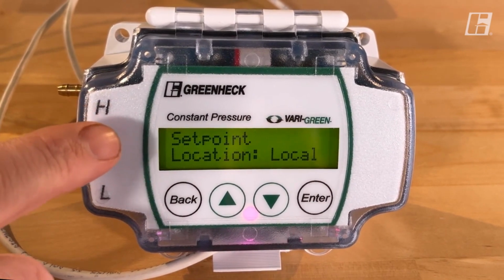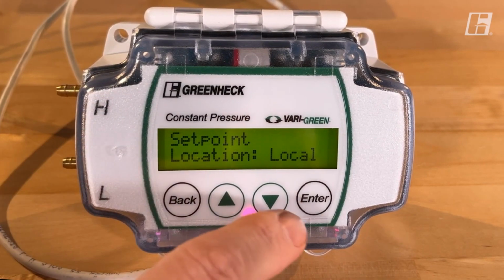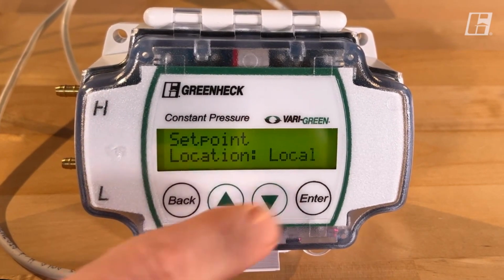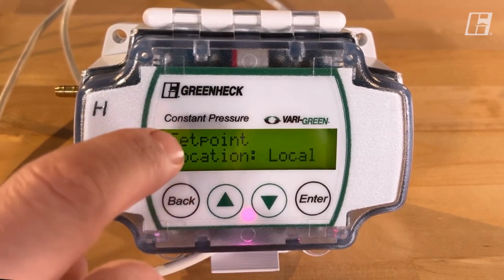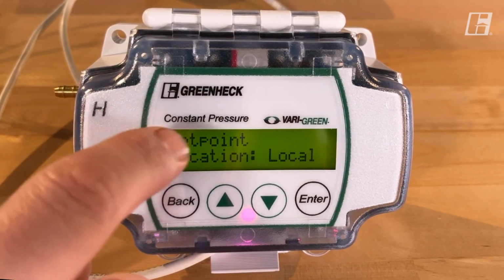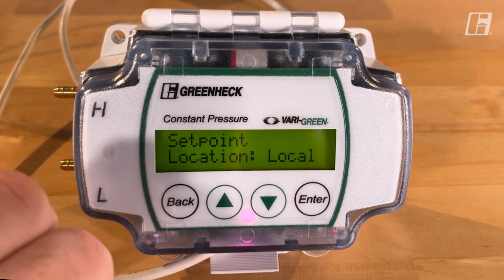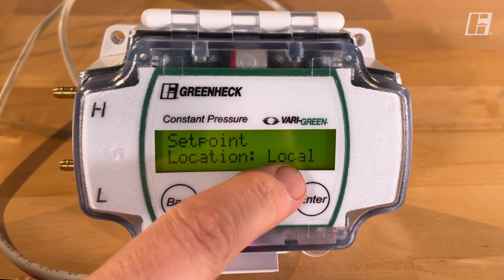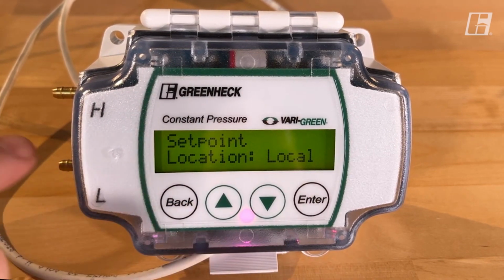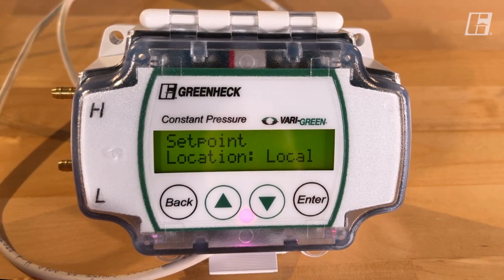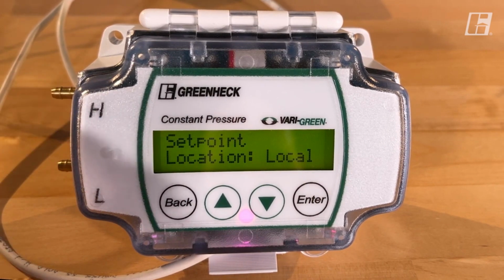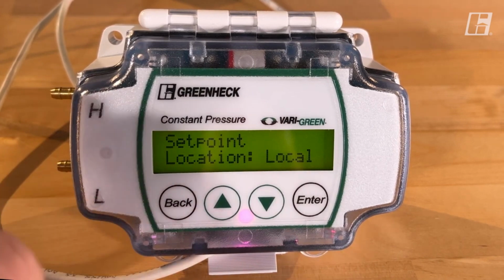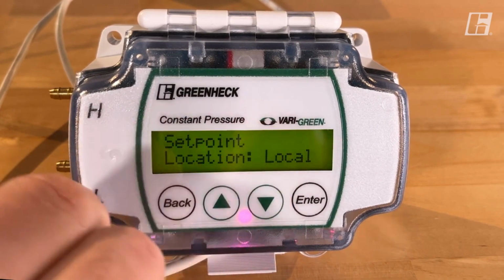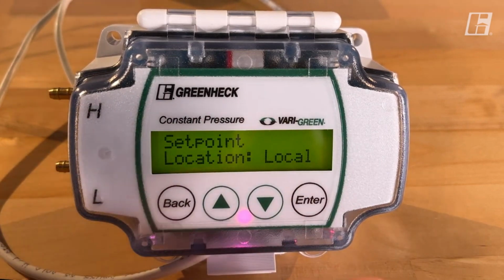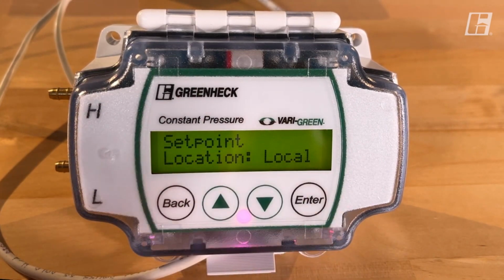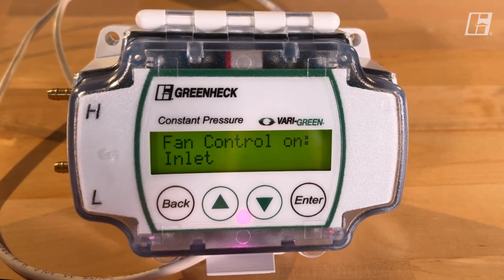Our next question is set point location, local or remote? What this is asking is, am I setting my set point on the screen here? We set it at -0.06 inches, so that's local. If I was using the remote set point terminal inside of this, and a building management system was telling it what its new pressure was, then you would use remote. 99% of installations will use the local setting here.